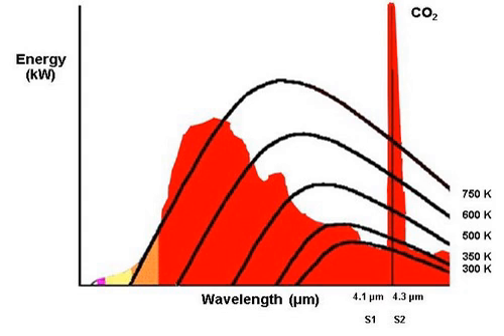Heat radiation. Infrared flame detectors suffer from infrared heat radiation which is not emitted by the possible fire. One could say that the fire can be masked by other heat sources. All objects which have a temperature higher than the absolute minimum temperature of 0 kelvins, or -273.15 degrees Celsius, emit energy, and at room temperature, 300 K, this heat is already a problem for the infrared flame detectors with the highest sensitivity. Sometimes a moving hand is sufficient to trigger an IR flame detector.